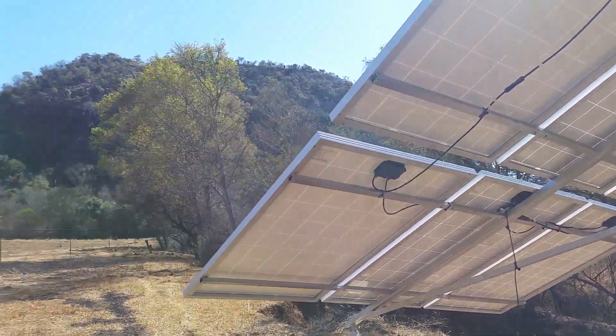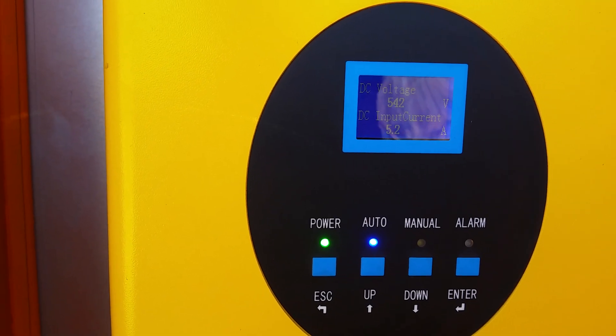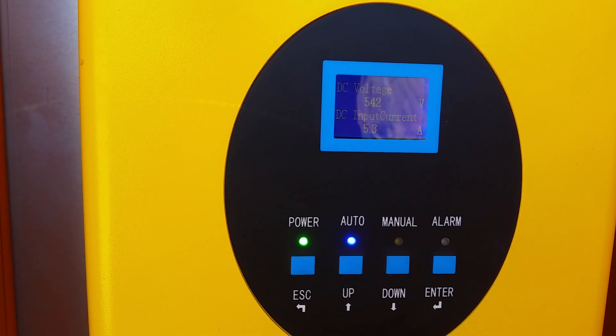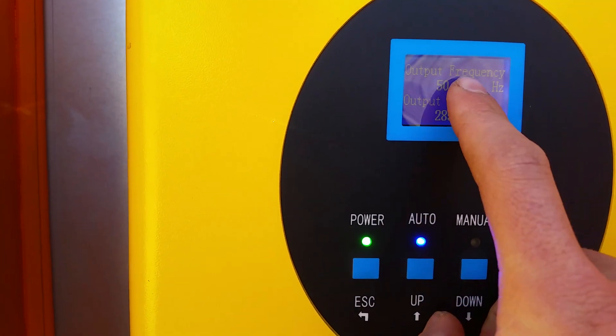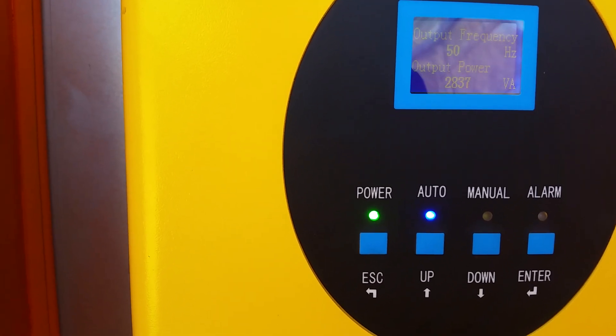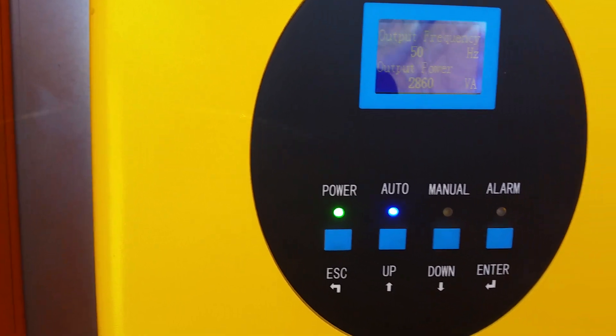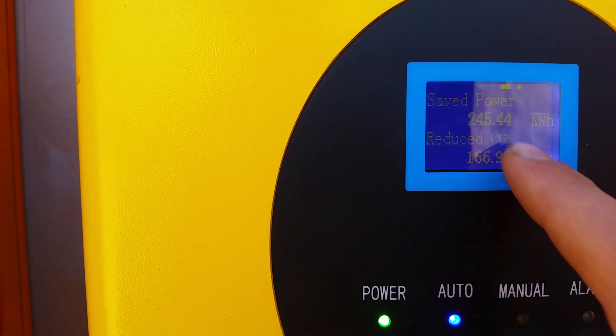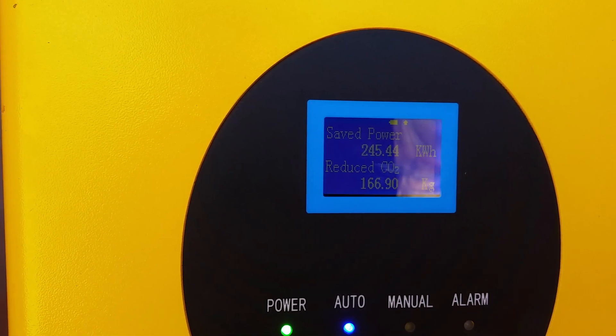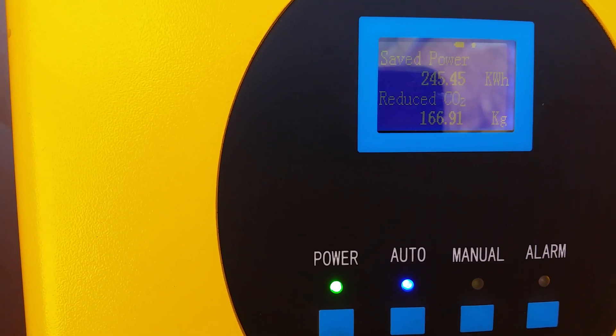The solar panel power comes to this type of inverter. The DC voltage is about 552 volts, and my output current is 5.3 amps at 3-phase. My pump's frequency is 50 hertz, and output power is 2855 watts. That's the amount of power I've already saved from running this pump — it's been about 4 days now, so 245.4 kilowatt hours. Reduced CO2 emissions is about 166.91 kilograms.